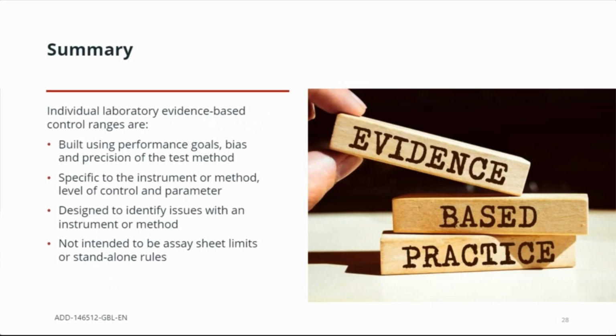In summary, our individual laboratory evidence-based control ranges are built using performance goals. That means bias and precision of the test method is known, documented, and evaluated on a routine basis. They are specific to the instrument or method and level of control. Again, all with the idea to alert users to problems that warrant investigation, issues that we truly want to investigate, and they're not intended to be assay sheet limits or standalone rules. So in summary, they are scientifically valid.